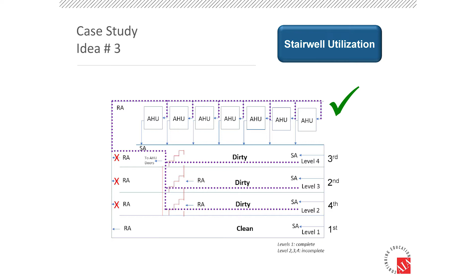So this is what we actually ended up doing, third time's the charm. Let's close the return air dampers on 2, 3, and 4 at the riser, isolate the return on those floors, and open the stairwell doors on those floors to let that be the path for the return air. That way, you give all the conditioned air that you need to those floors, but you're still maintaining the integrity of your ductwork at the time.